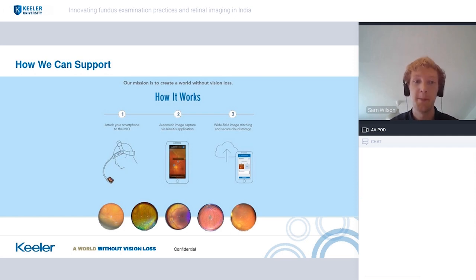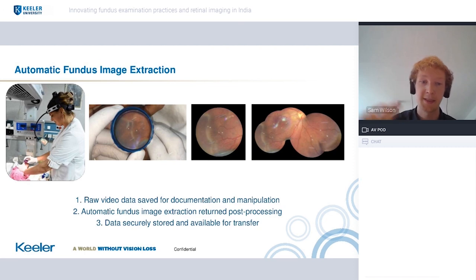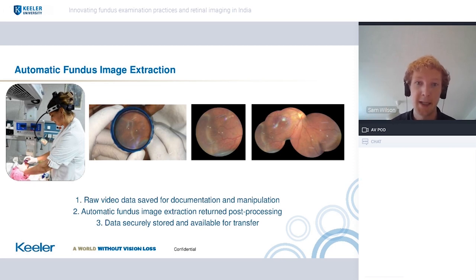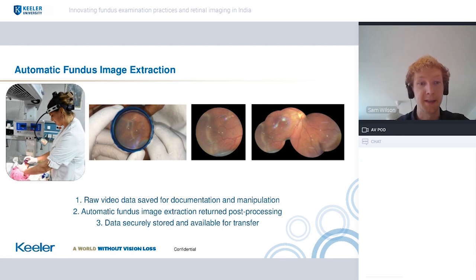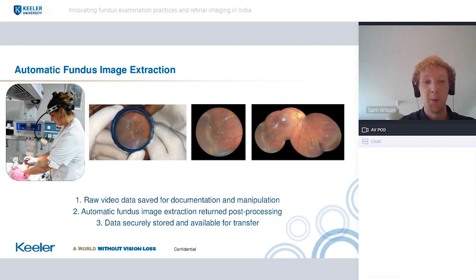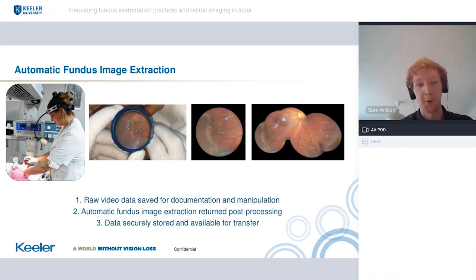This isn't stereoscopic, but one of the key parts is that you're still able to do the examination, and the clever part is that you're able to automatically get that fundus image out. Here's an example from one of those doctors, Gabriela, in Argentina. You can see she is examining a baby for retinopathy of prematurity and she's wearing a device on her head. What she sees is the smartphone screen, using the smartphone flashlight to examine the retina. This is conducted as a live video during the examination. From a frame captured from that video, we can automatically extract a singular fundus image. We're also working on a beta function to integrate that into a wide-field view of the fundus, as you can see on the right.